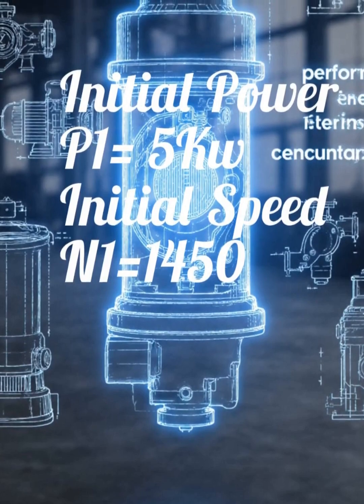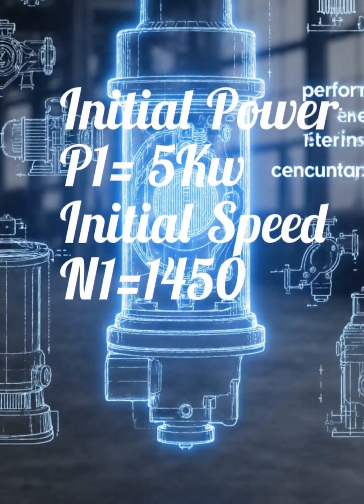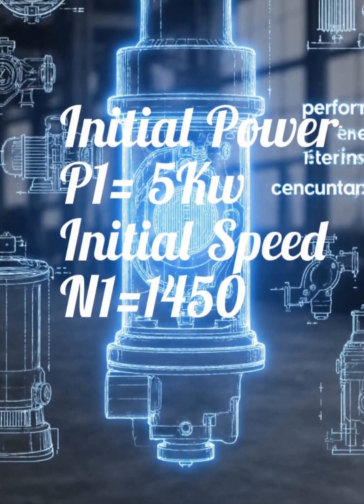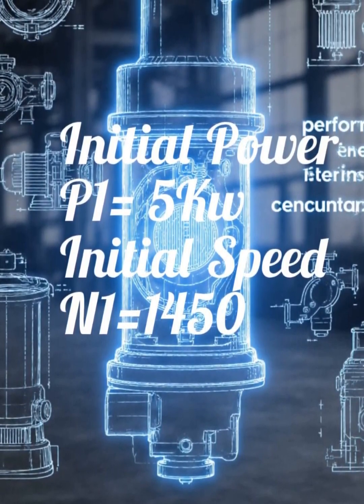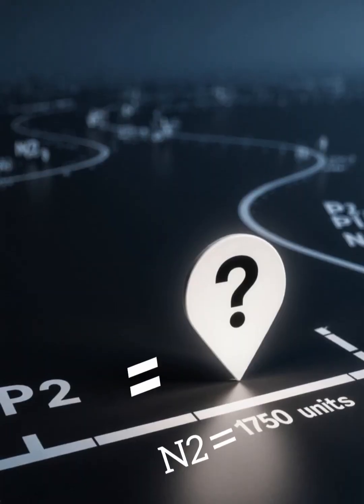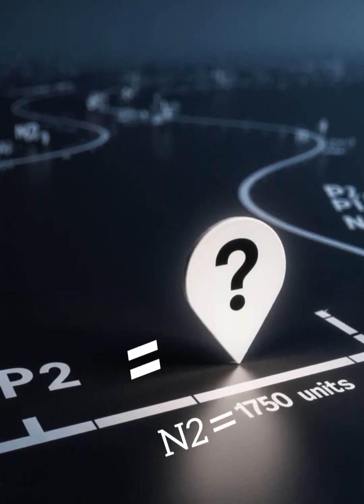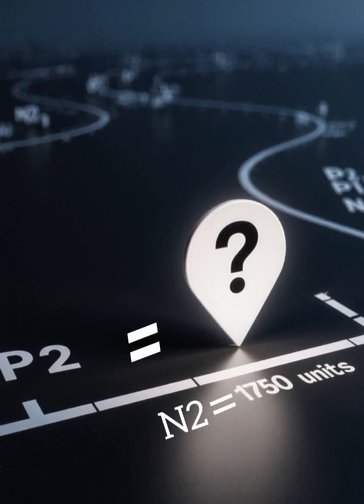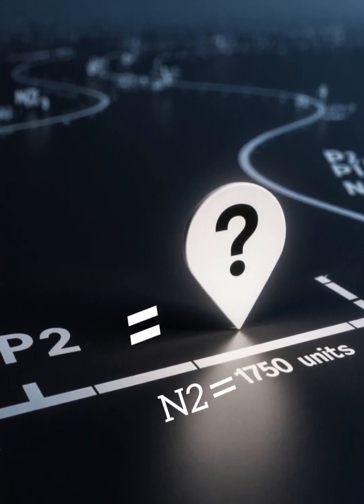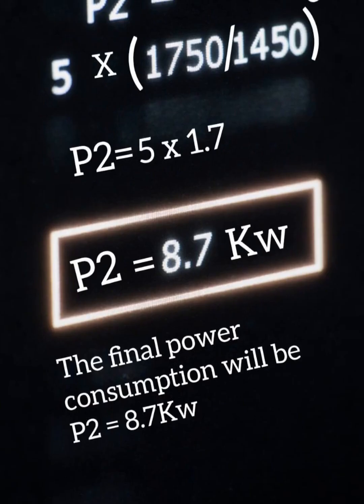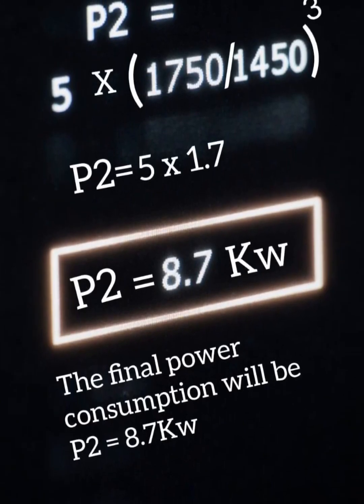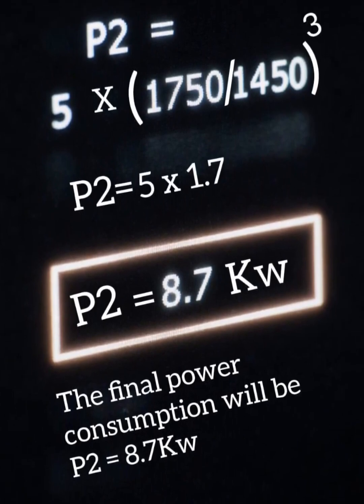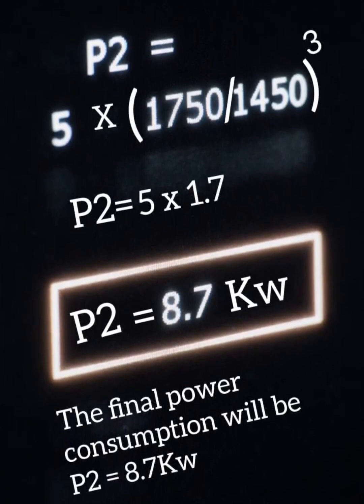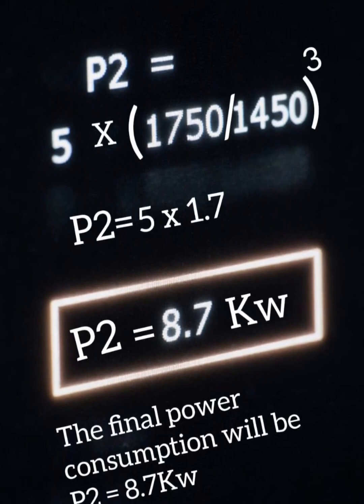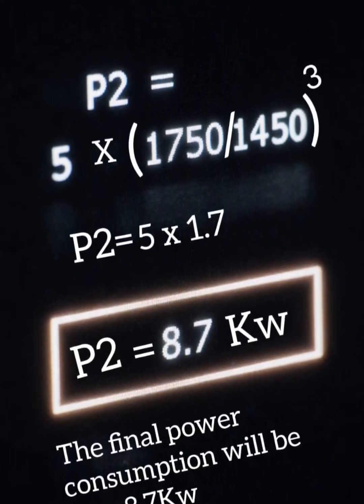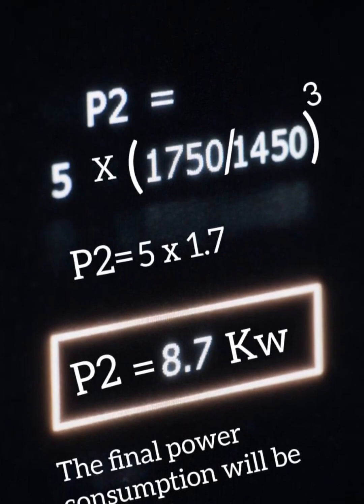Given an initial power, P1, of 5 kilowatts at speed N1 of 1,450, to find the new power, P2, at a speed N2 of 1,750, we apply the formula. Substituting the values, P2 equals 5 times 1,750 over 1,450, the whole power 3, which calculates to approximately 8.7 kilowatts.